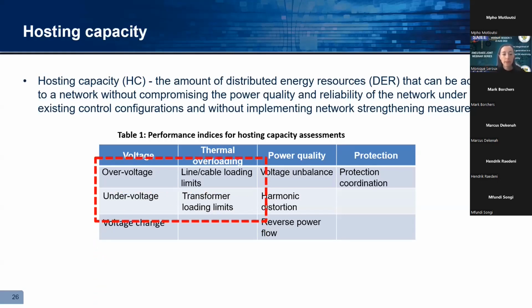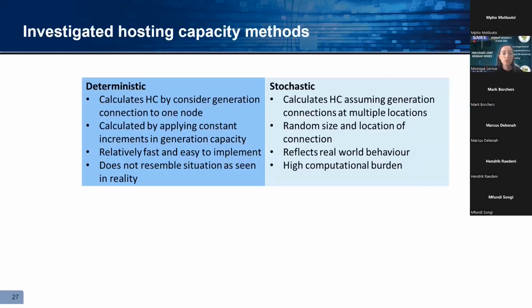So for this tool and for the standard calculations that are done on distribution networks, where the generator plant is connected quite close to the substation or close to the bus bar, the main violations that you're looking at are over voltage and under voltage, and then thermal limits on the lines and the transformers. And that's what this tool used to determine the hosting capacity, how much generation can be added to a network. Okay, so we used two different methods to determine the hosting capacity on a distribution network.